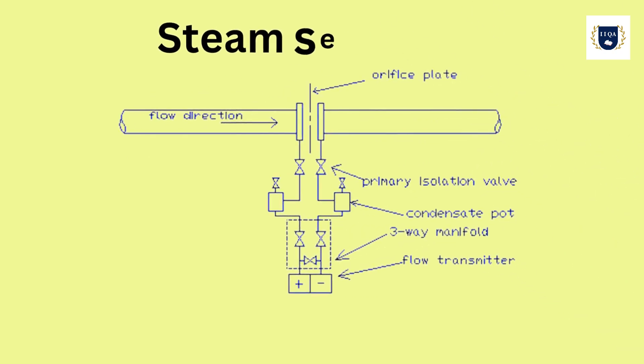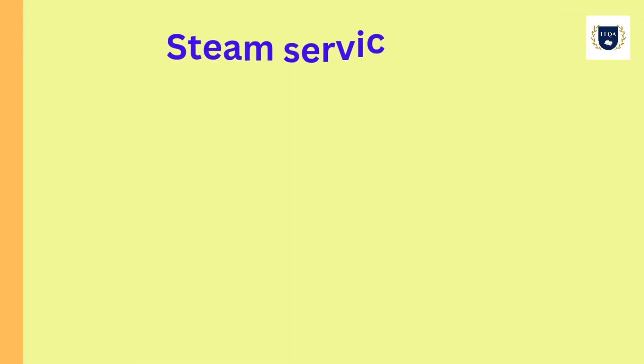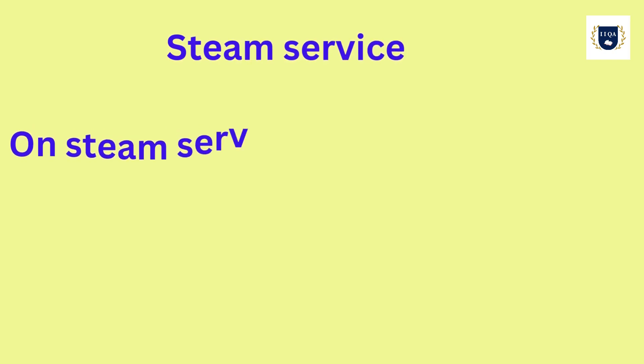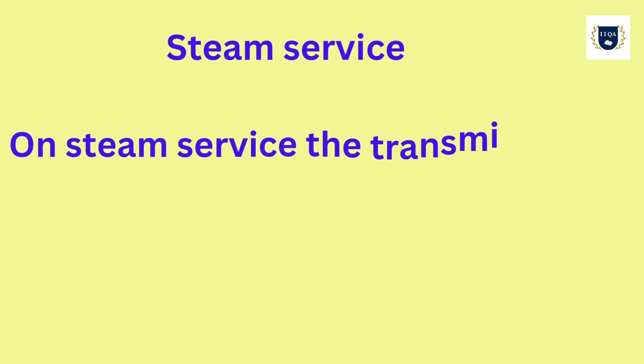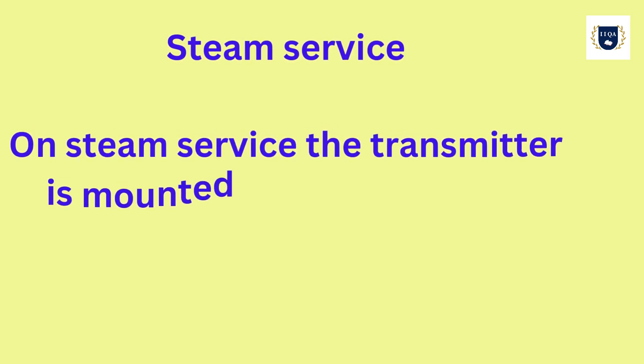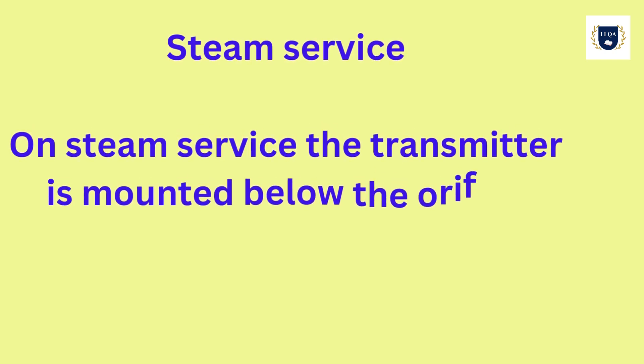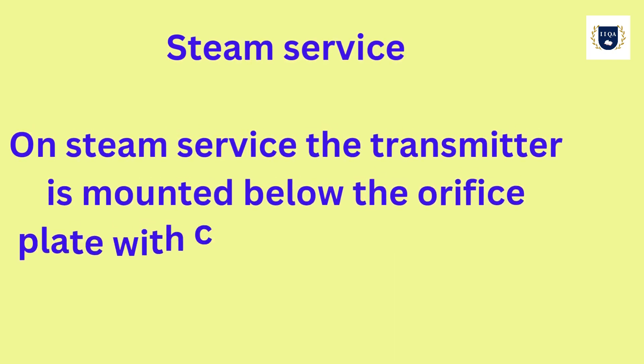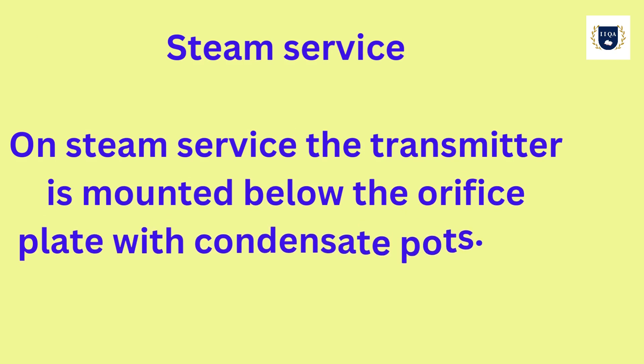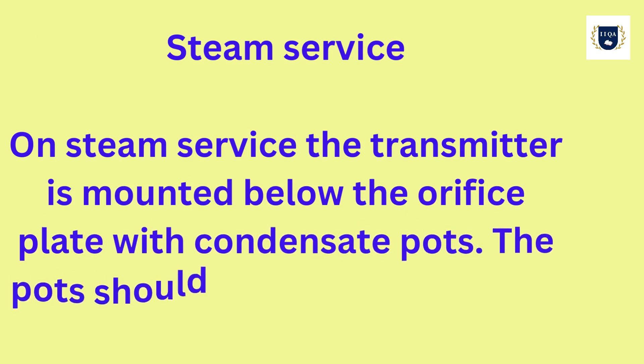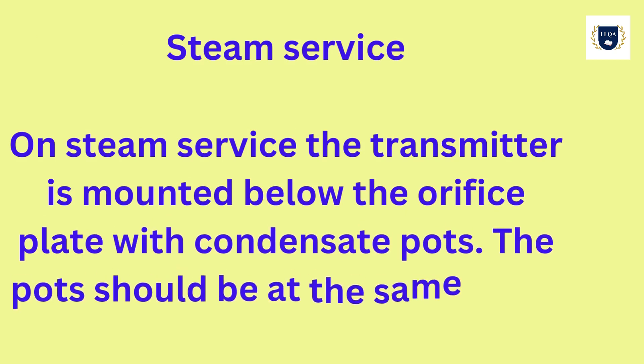Steam Service. On steam service, the transmitter is mounted below the orifice plate with condensate pots. The pots should be at the same level.